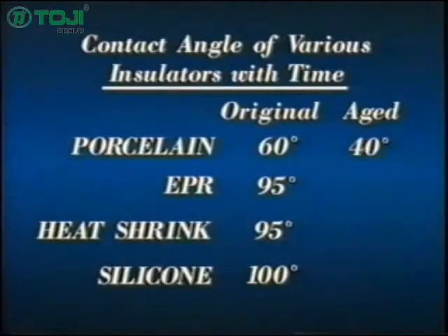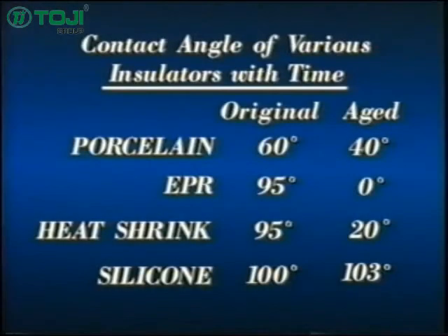As porcelain, EPR rubber, and heat shrink materials age and are subjected to leakage currents, they become even more hydrophilic, resulting in much smaller contact angles. This causes the surface to be continually wet, which results in additional surface degradation. Not only does silicone have the best contact angle at the start of the life of the product, but the contact angle stays relatively constant with age. This is because silicone rubber has the unique capability to regenerate its hydrophobicity, even after it has been exposed to high leakage currents.